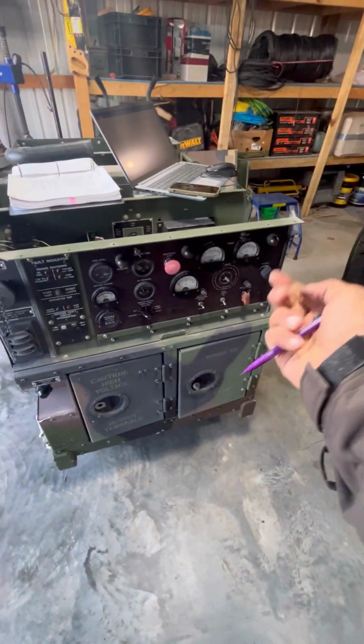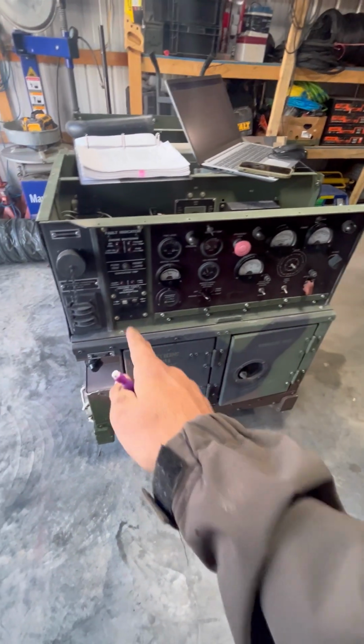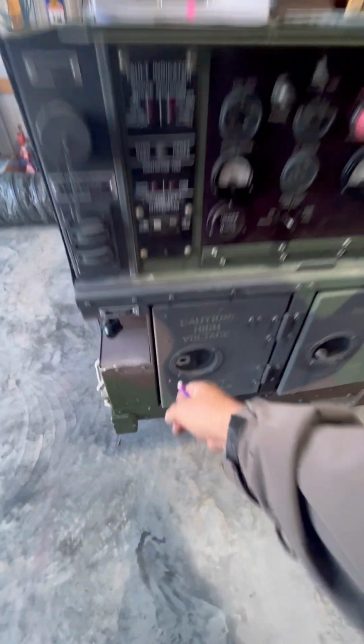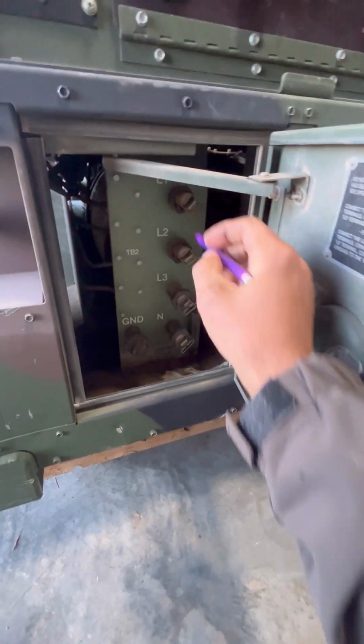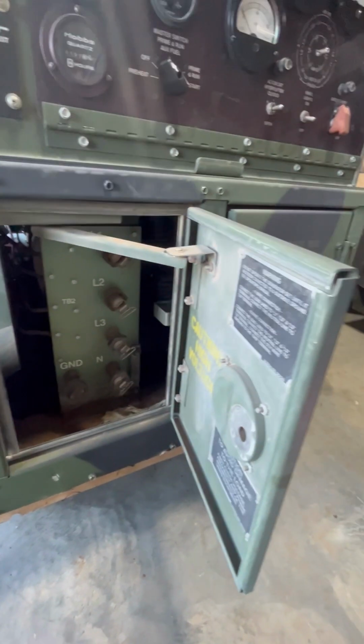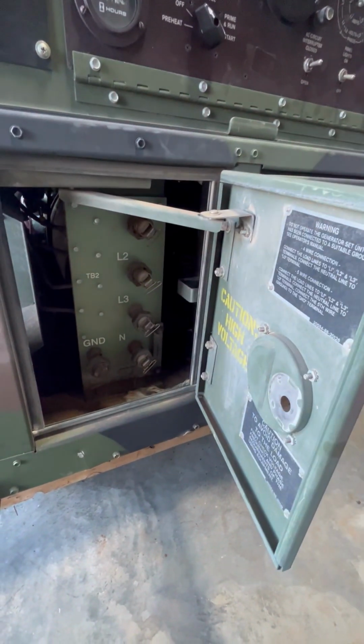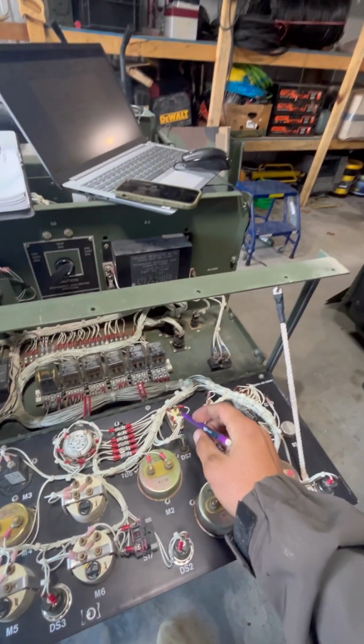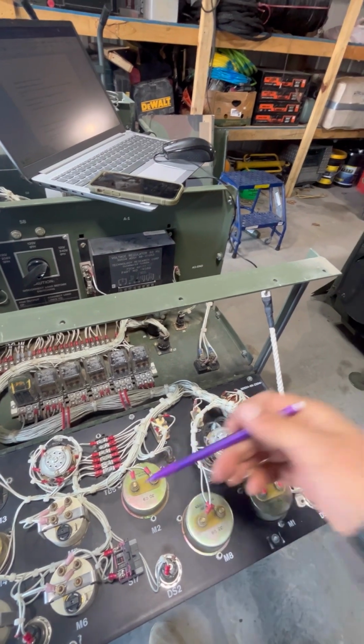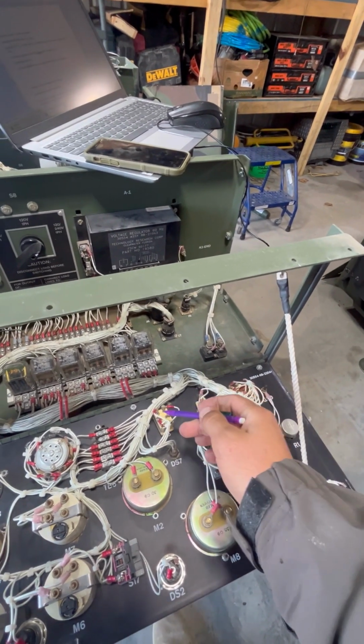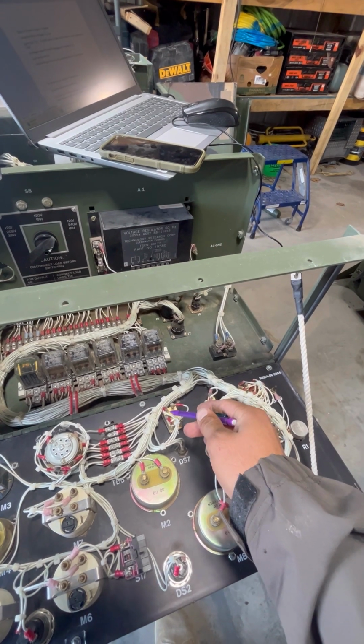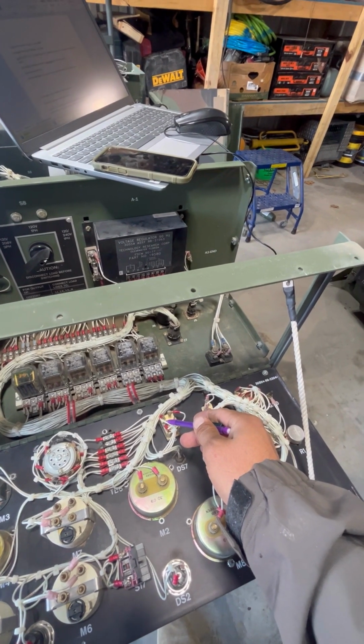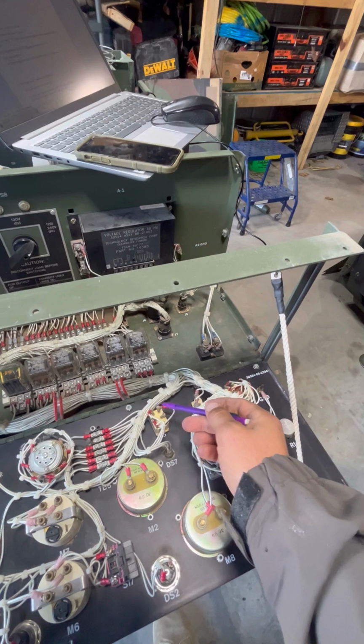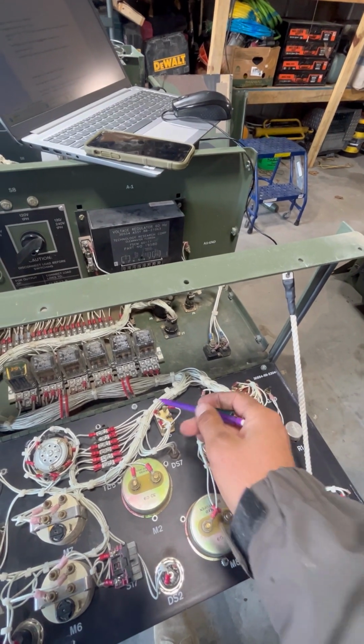I closed the circuit. It stayed closed, and I was getting 240 volts between lug 1 and lug 3. I only checked lug 1 and lug 3 in the single phase 240 position, but I'm sure everything else works. That diode is probably something somebody from the military pulled off of this to rob and donate to another generator they had. And that diode is 20 cents, maybe 90 cents. And if you don't have that diode, your generator's not producing power.